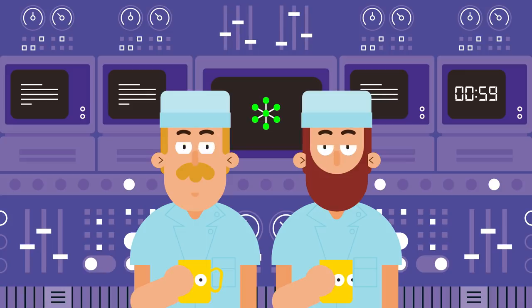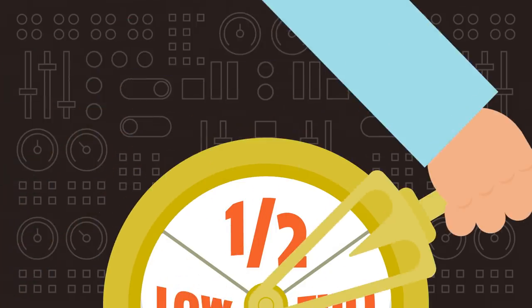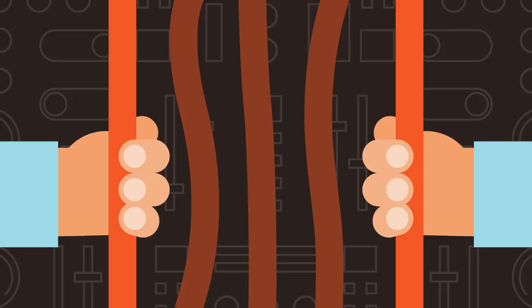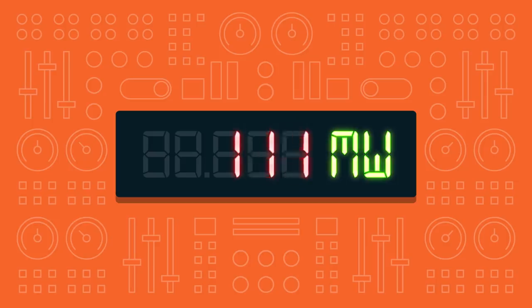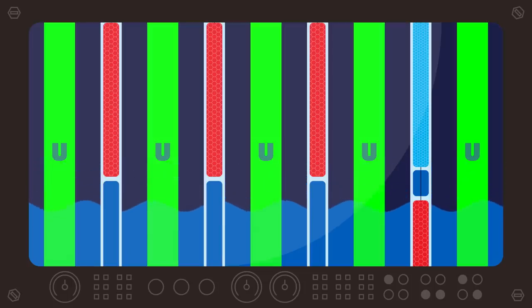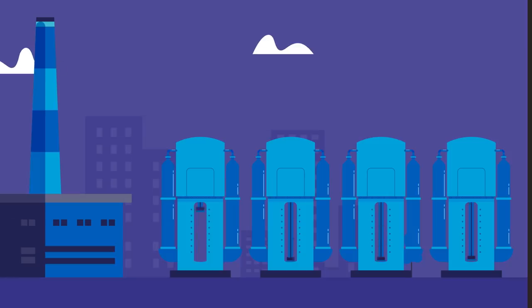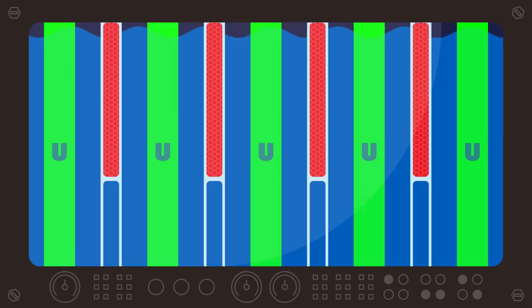Because of this, about an hour into the test, the power suddenly plummeted to an extremely dangerous level of 30 megawatts. Control room personnel decided to increase the power by disconnecting most of the reactor control rods from the automatic control system and manually extracting almost all rods to their upper limits. This increased power back to 200 megawatts, so they decided to proceed with the test at that level. Because of the low operating power, water levels were insufficient, so extra water pumps were activated to increase water flow, and to counteract the absorbing effects of the water, they removed even more manual control rods to maintain power.